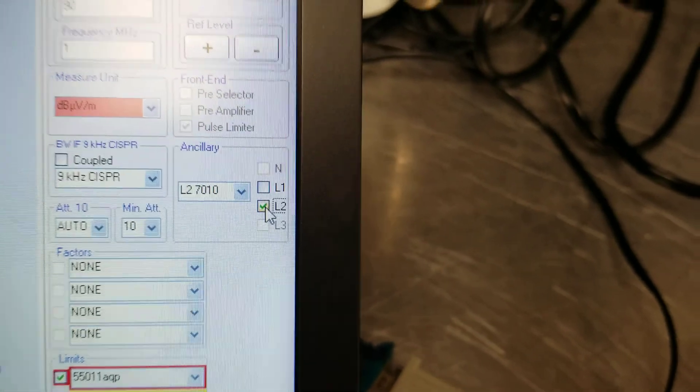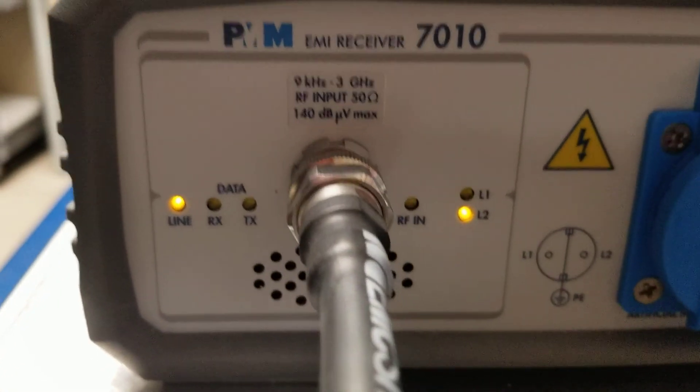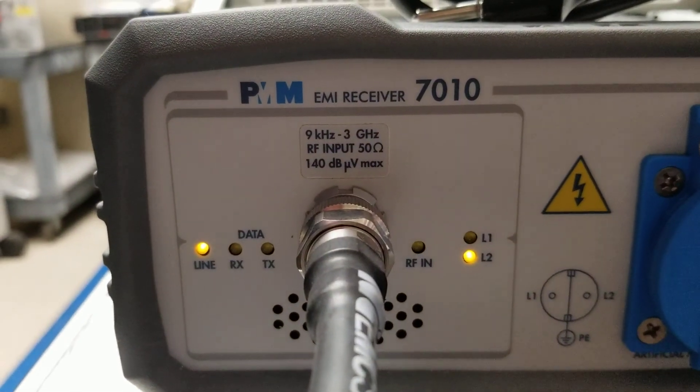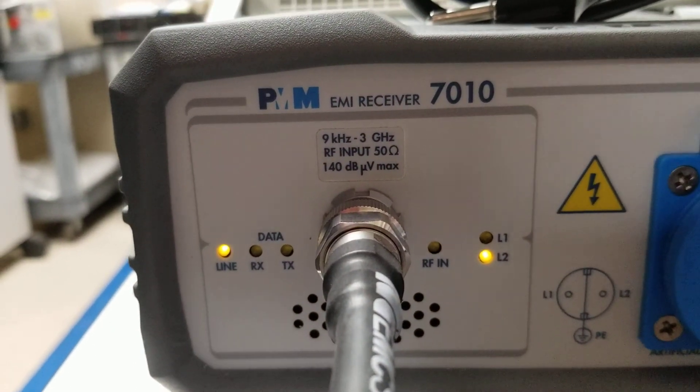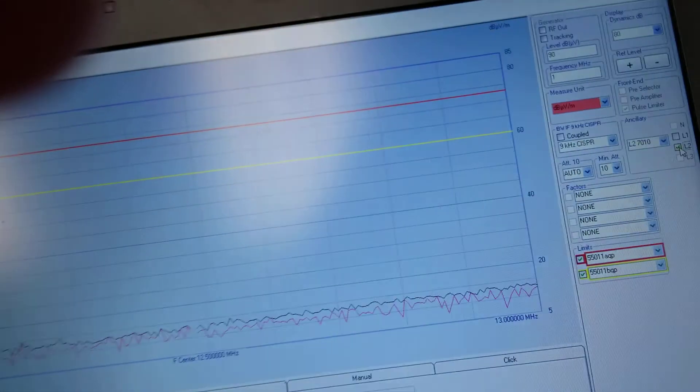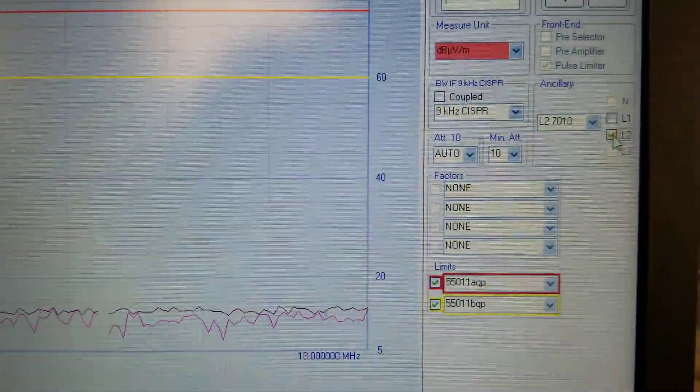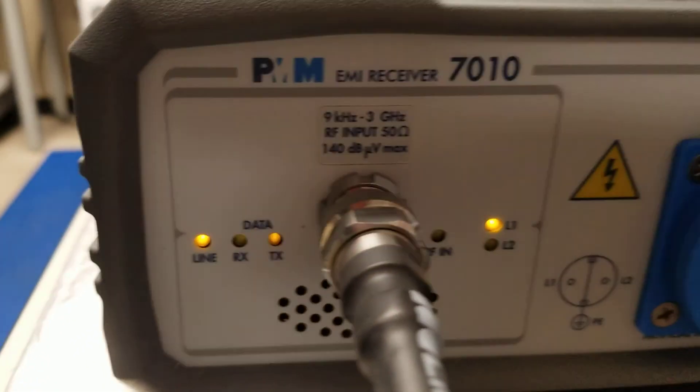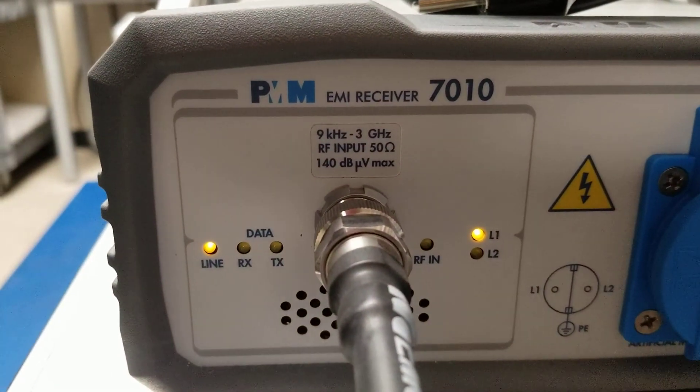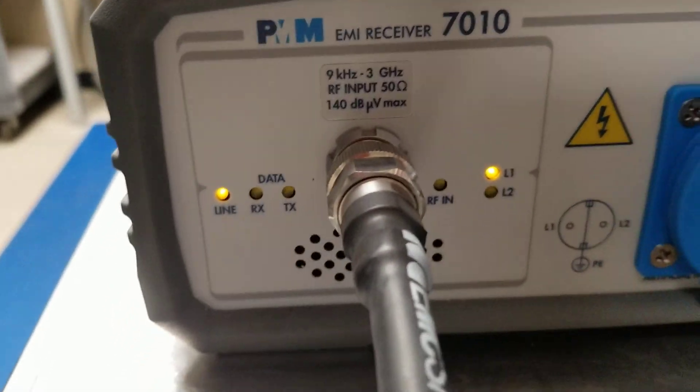We will choose line 2 at this point to test, and you will see that there is an indicator light on the front of the 7010 showing you have chosen line 2. When we choose line 1, it will do the same thing. The indicator light will let us know that we have chosen line 1, and those are the lines that will have the interference induced into it.